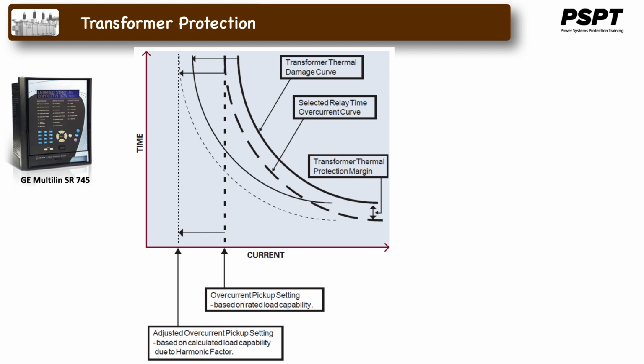A variety of standard time current curves and defined times are provided. Flex curves coordinate with the adjacent protections, including fuses, as well as transformer damage curves and thermal damage curves for downstream equipment.